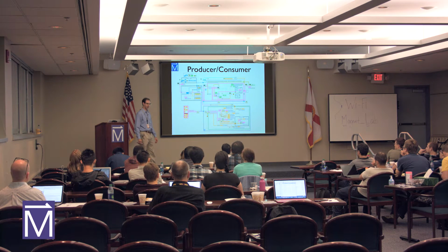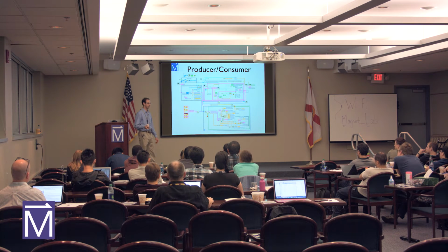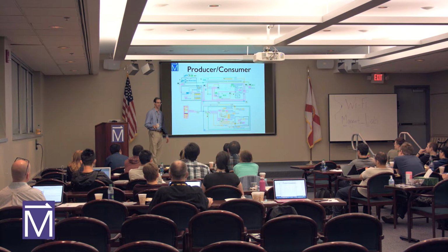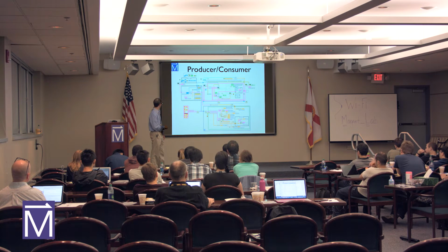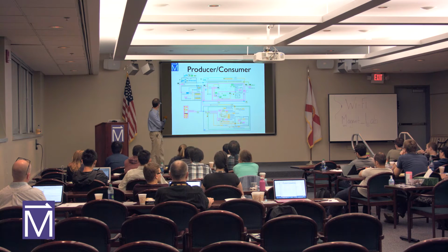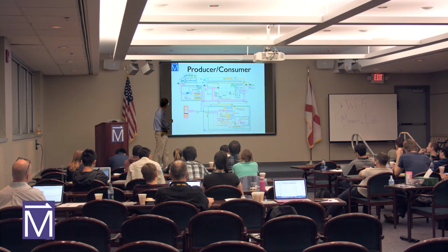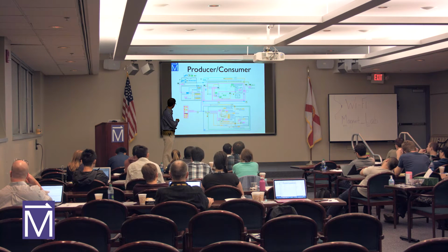Its job is to watch the magnet. And I guess some of you experienced this in Cell 9 when the welders drew an arc and the magnet protection system didn't like it very much, and so it tripped the magnet off. It said there's a voltage spike. This is bad. That's this code that did that. So let's see, what's going on here? We open some files and read in some parameters, and then we create this thing called a queue there.